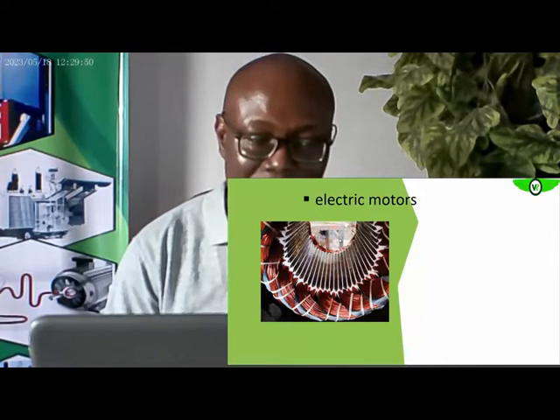So next we are going to look at electric motor. When we carry out insulation resistance test on electric motor, what are we actually testing? If you look at the electric motor, you will see that it is made up of windings. These windings are laid in what is called the slot in the stator, or the stator yoke, as it's called. As you can see on your screen, this is the stator yoke and these are the slots.